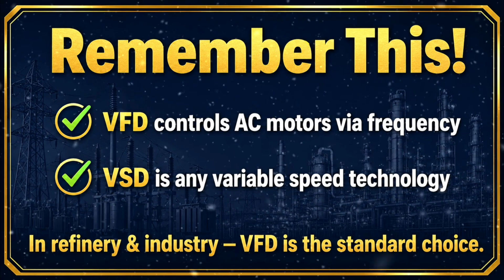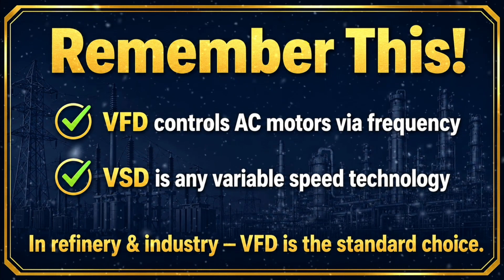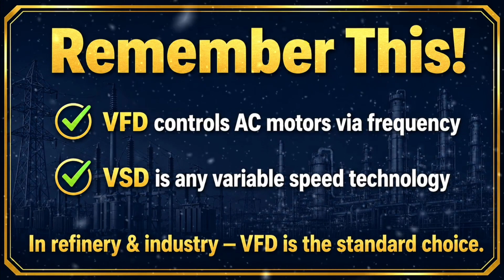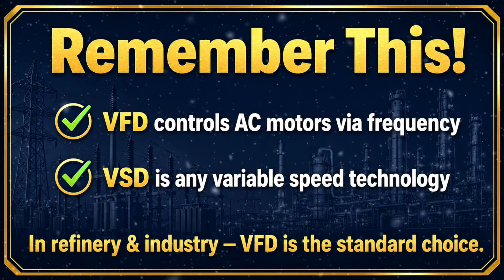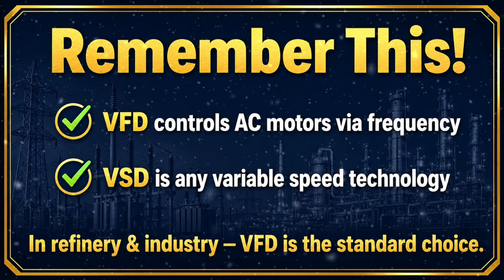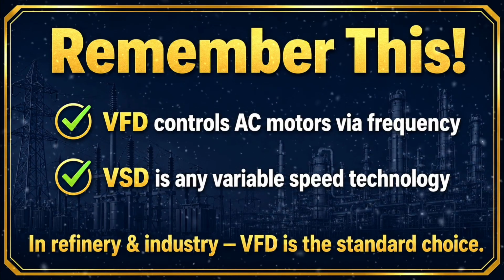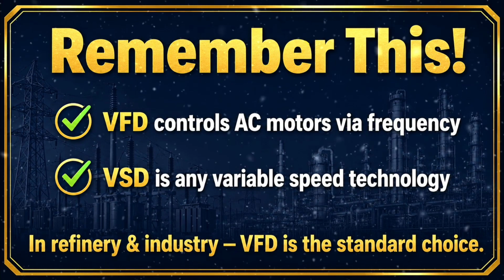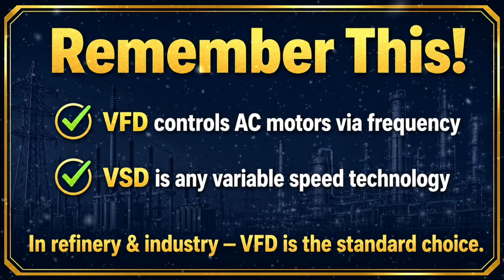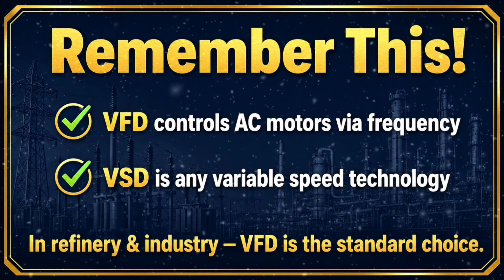Let us now summarize the key benefits of VFD. Benefit 1. Energy saving. In variable torque loads, fans and pumps, VFD can save up to 50% of energy compared to running the motor at full fixed speed with throttle control. Affinity law. Reduce speed by 20%, power reduces by approximately 50%. This is the cubic law relationship. P is proportional to N cubed.